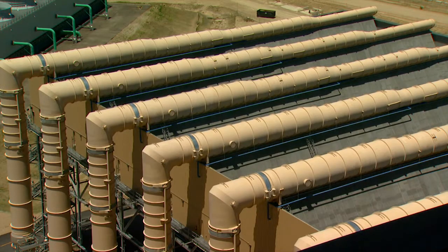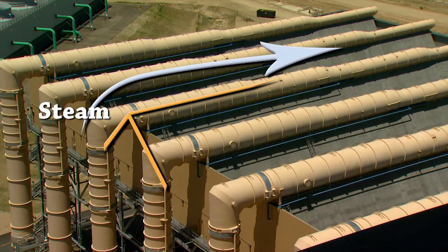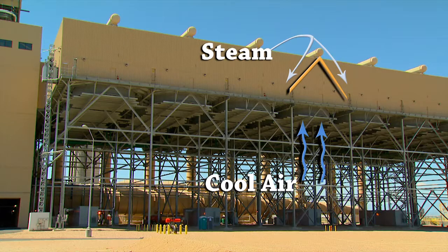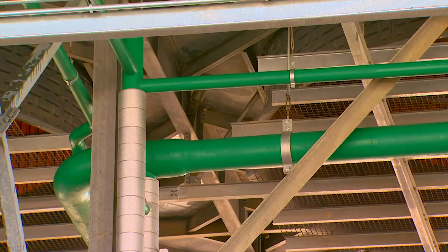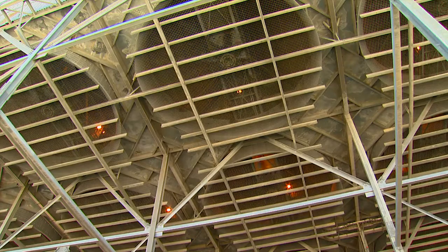The air-cooled condenser is an A-frame. So if you think of an A-frame type cabin, at the top of the roof is where the steam comes down, it goes down the sides of the roof. The air is coming up from below, goes through that roof, cooling off the steam, and the condensate is collected down at the bottom of the roof, and that goes back into the cycle.